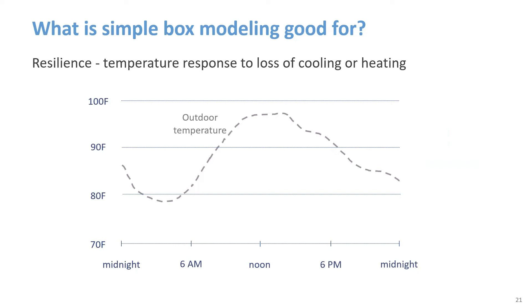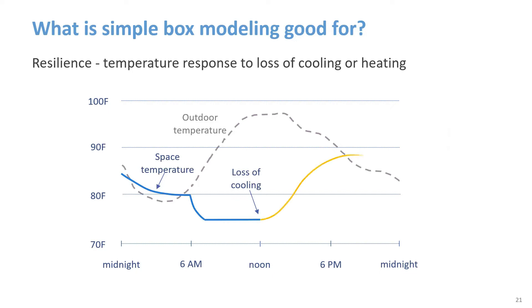Resilience is becoming a more important issue for building designers. Energy modeling programs can provide a rough estimate of space temperature and how it might change when there's a loss of cooling, which might be due to a power outage or system failure. This illustration shows one hot day under normal operation, and if cooling is lost at noon, the space temperature will rise at different rates depending on whether the space has low or high thermal mass. The simulation can estimate how long the space temperature will remain comfortable in both cases.